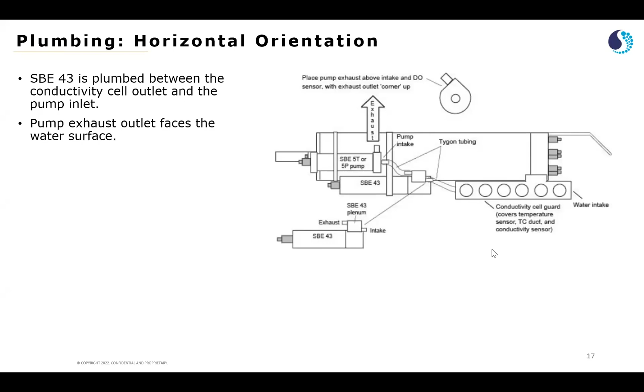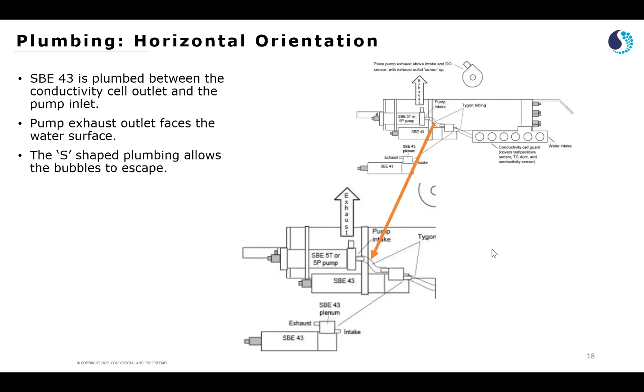Between the horizontal and vertical orientation, take a look at how the Tygon tubing is fitted in this particular section. It's like an S or S-shaped, and let's take a closer look at it. It is important to have the Tygon tubing placed this way, like a staircase or an S shape, because it is important for the bubbles to escape through the exhaust. Because if the bubbles stay in the system, you'll have errors in the data.